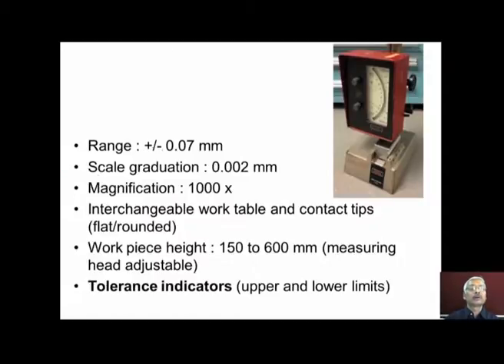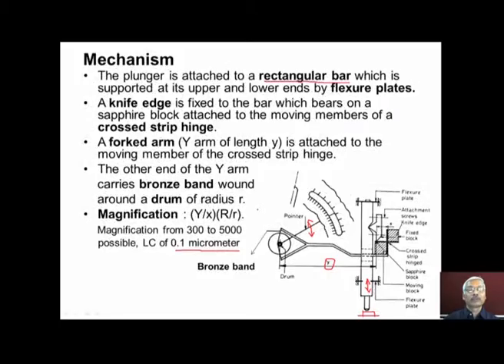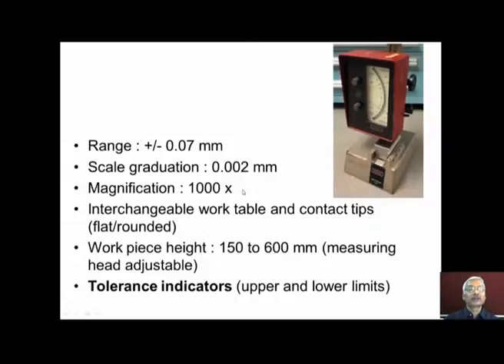Range varies from minus 0.07 to plus 0.07, and the scale graduation is 0.002 millimeter. Magnification of 1000 and up to 5000 is possible, and then we have an interchangeable work table. Depending upon the workpiece, these tables can be changed, and the contact tips, the plunger end which makes contact with the workpiece, are replaceable. We can have a flat end contact tip or a rounded end contact tip like this. That depends upon the type of workpiece to be inspected.